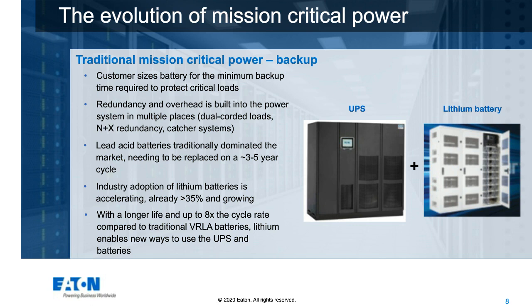And that's an activity that doesn't happen that often here in North America. It's a rather uncommon event to see a power outage that lasts more than a few seconds. But it's still extremely critical that it work and that it work every time. So redundancy and overhead are built into the power system. In multiple places we use dual-corded architectures and plus-one redundancy catcher systems, all kinds of elaborate ways to make sure that we always maintain critical battery-backed-up power into that data center.